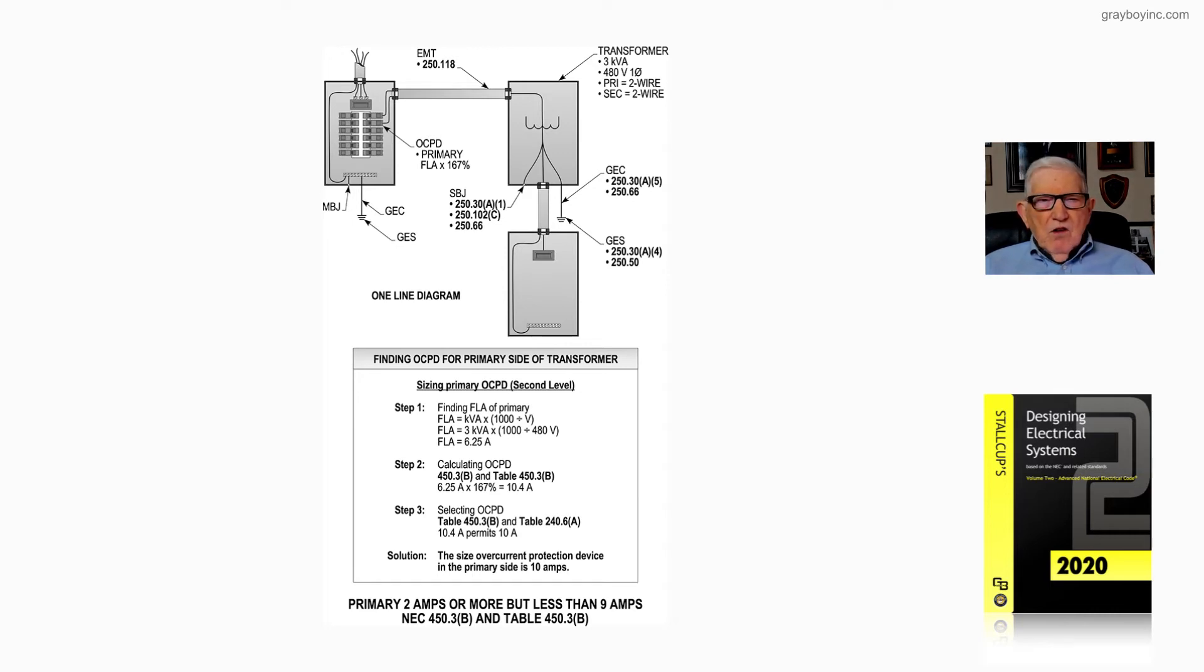But now, the grounding is the same, we're going to have a supply side bonding jumper here, because it's not at the service, it's at a separately derived system location.